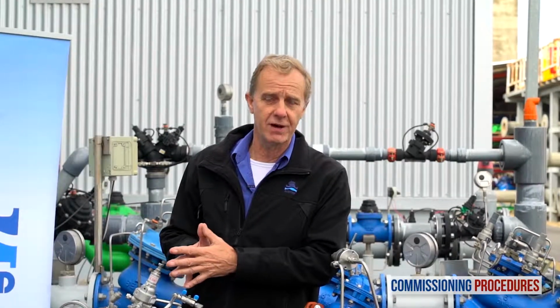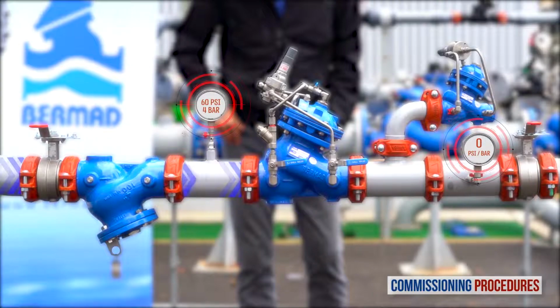On the other hand, if you're prepared for pressure calibration by releasing the pilot screw of the reducing valve or tightening the pilot screw of the relief valve, water won't flow through the station. The reason is that in this case, the pressure reducing valve will have closed shortly after introducing flow to the station.